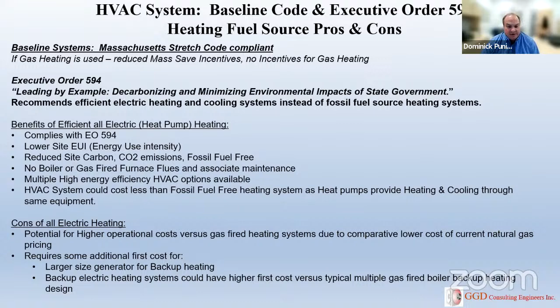All the different HVAC options, it's important that they're apples to apples. So what we wanted to do was at least present the proposed design criteria. And this is largely based upon the Massachusetts Energy Code. What we would propose is, on a heating condition of 5 degrees of outdoor air, that we would be heating all spaces to 70 degrees and allow a user adjustment of plus or minus 2 degrees. And then for the cooling system, we would design to an outdoor day of 91 degrees dry bulb and 73 degrees wet bulb, with wet bulb being a factor of outdoor humidity levels. The inside would be 75 degrees dry bulb, plus or minus 2 degrees set point, and the relative humidity within the space would be 55% RH. So that's within what's called the comfort zone.